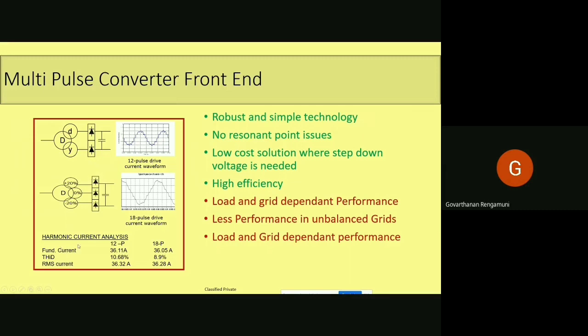So you can see the harmonic current analysis in the bottom. For the 12 pulse, the fundamental current is 36 ampere. The total harmonic distortion is 10.68. But when it comes to 18 pulse, it is 8.9 only. So if the pulse number increases, then you will be getting reduced current harmonics, reduced THD. So this is a robust and simple technology. No resonant point issues, low cost solution, and high efficiency.